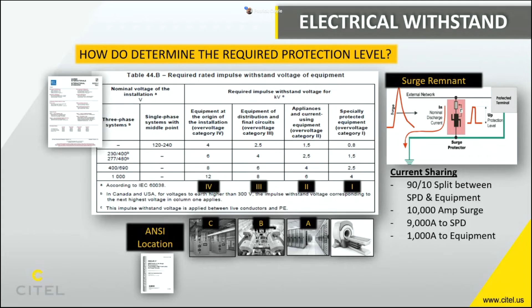The surge protector does not handle 100% of the surge, but what portion your equipment can survive is really something that's only sometimes known with testing. So here, if we said that equipment would survive 1,000 amps or less, we would need to have a 90-10 split between the SPD and the equipment. If we used a 10,000 amp surge, that would be 9,000 through the SPD and 1,000 through the equipment. So this is really just the maximum limit, but we really should keep it lower than that in order to extend the life of the equipment.